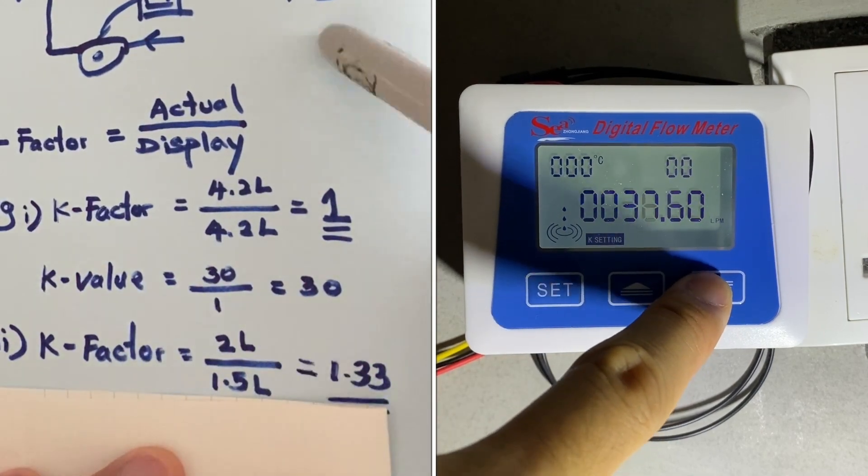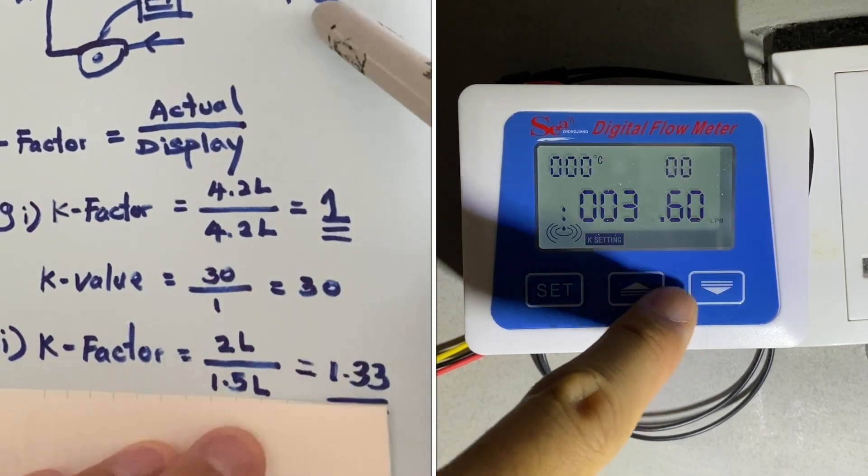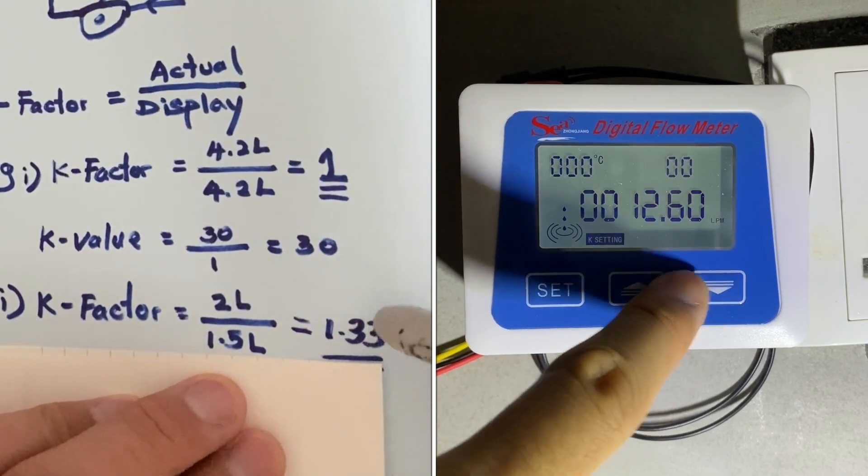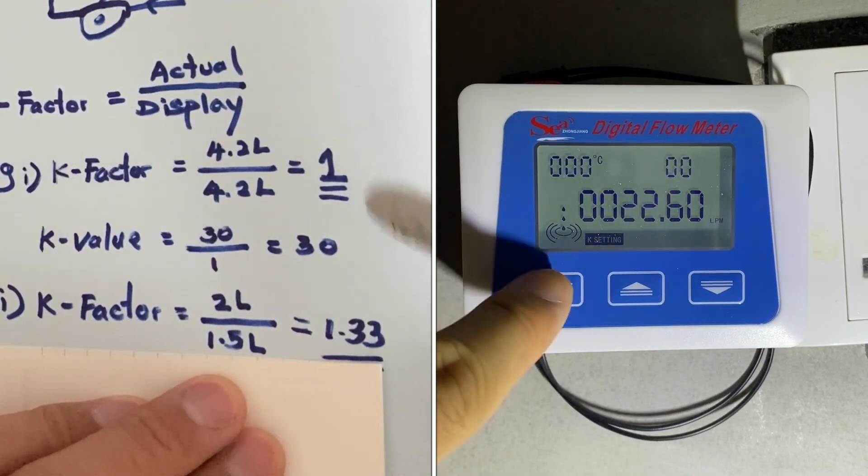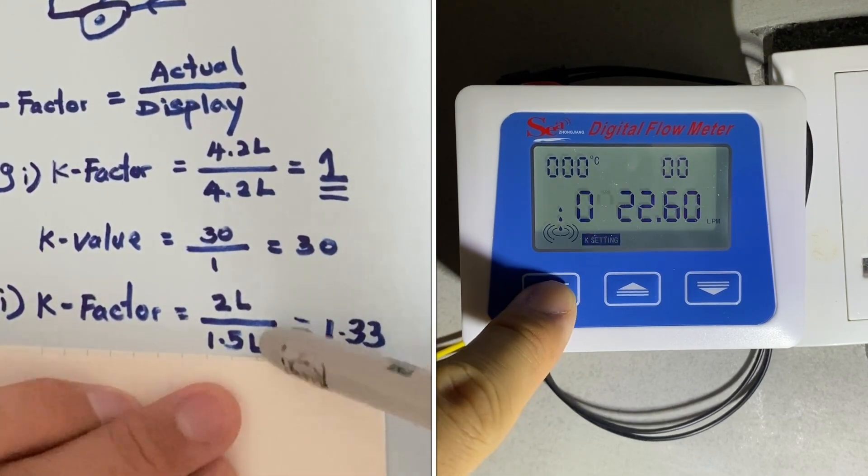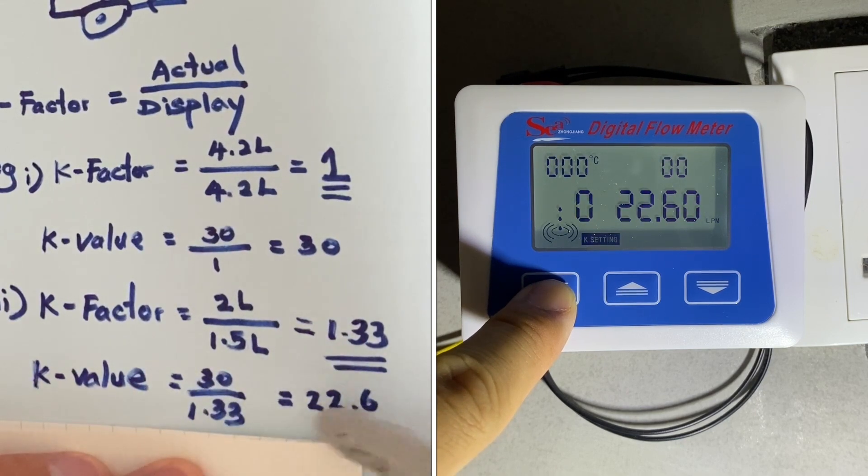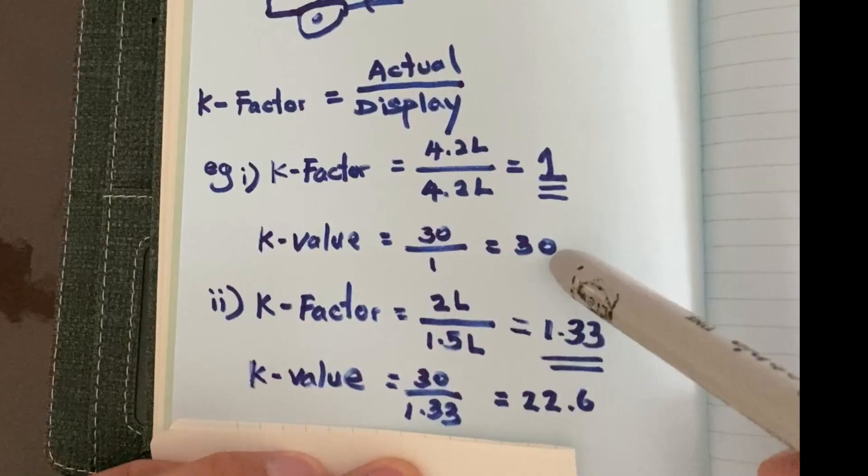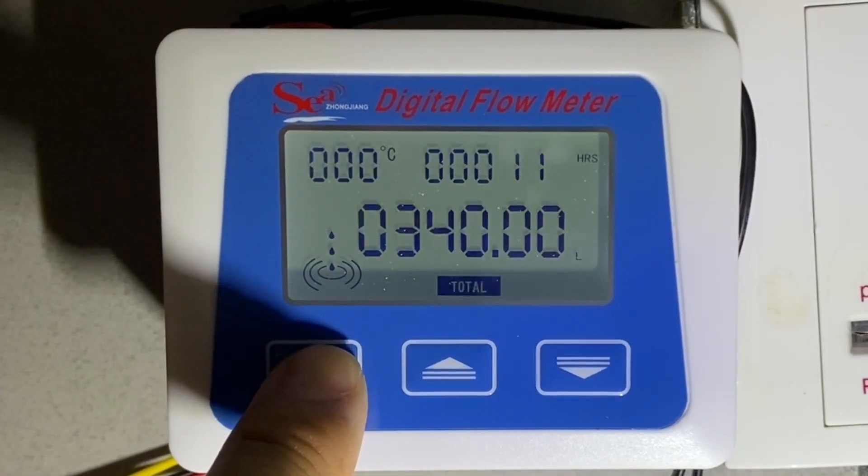Otherwise, if I manage to get 2 liters of water but it records only 1.5 liters, then you divide them, the value is more than 1. So all I need to do is reduce my K value. How to do that? I divide by 1.33, and that's the value that I need to reduce, up to 22.6.